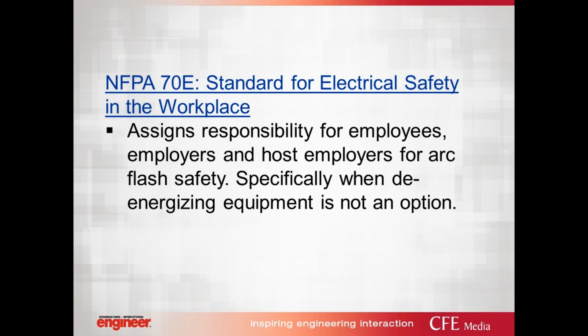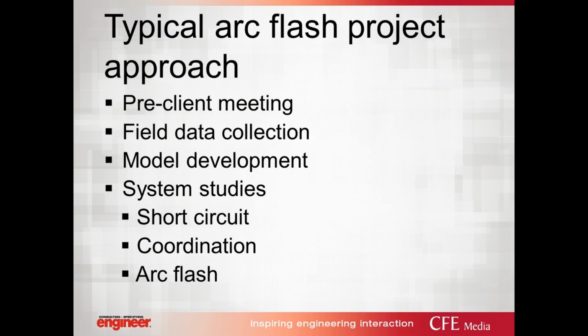NFPA 70E is the standard for electrical safety in the workplace. This assigns responsibility for employees and employers for arc flash safety, specifically when de-energizing equipment is not an option. This standard gives the required procedures for work protection and for PPE, and Annex D gives us the incident energy and arc flash boundary calculation methods, which are actually calculated off of IEEE 1584. While not a code, it is enforceable by OSHA. This is a standard that will typically go a long way towards compliance with OSHA requirements when setting up and managing your safety program. And with that, I will turn it over to Zia.